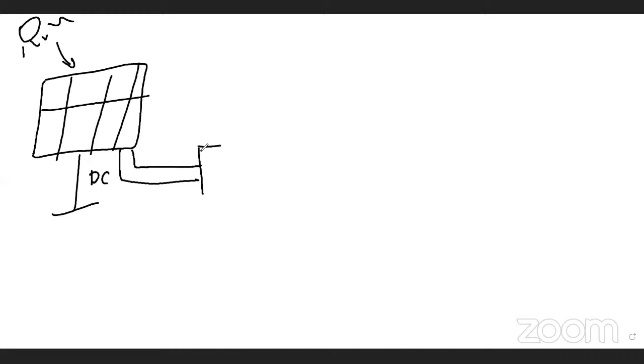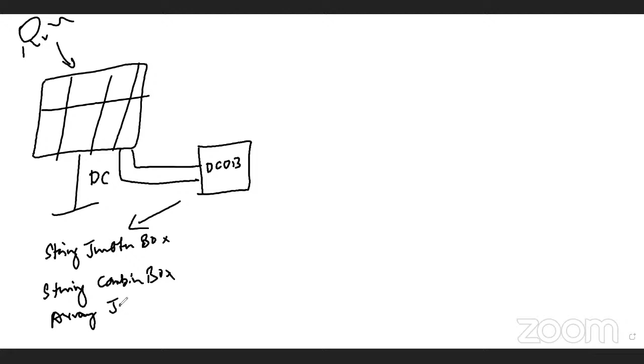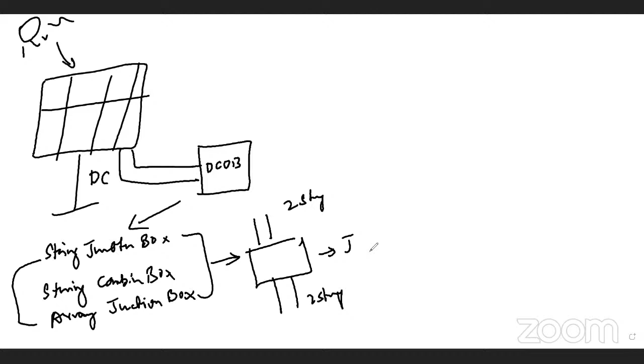When the sunlight falls, it produces DC power. The DC power actually comes to the DCDB box, which is called the DC distribution box. The DCDB can be called a string junction box, or can be called a string combiner box, or can be called an array junction box. Whenever it is referred to as a junction box, it means the number of inputs coming into the box and the number of outputs going out of the box should be the same. Let's say 2 strings coming in, 2 strings going out - so this is the junction box.